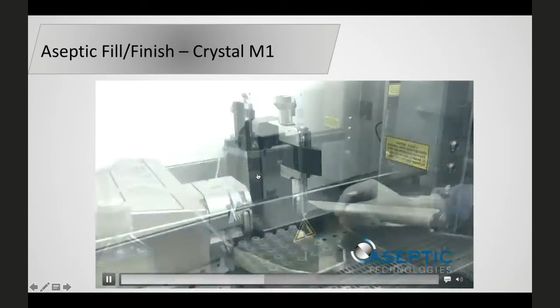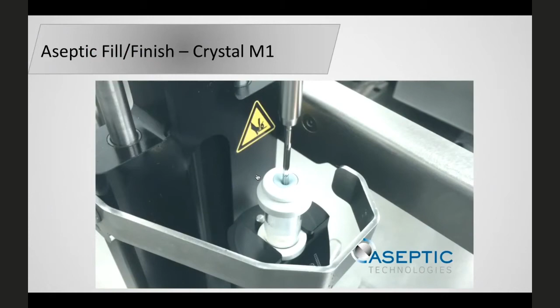So I'm not sure if this video is going to show up very well. It wasn't streaming very well, but I just wanted to quickly show a video of what the system that we have now looks like. So it uses a peristaltic pump. It's got a completely disposable tubing system with the needle attached already that you would install in this system. And then you set up the volumes that are going to be dispensed. So you choose your volume and vial based on the project. Then this is the semi-automated part. You have to manually put the vial on the system, pull down the lever, and it dispenses into the vial.